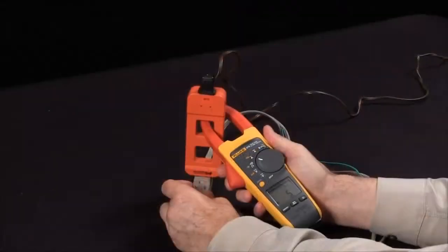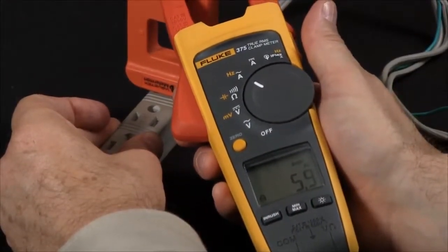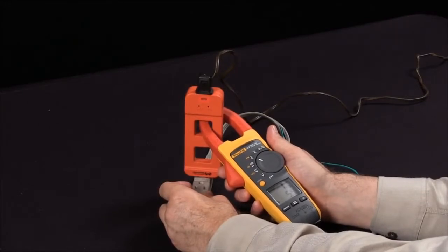I can go through my x10 winding, and there I'm reading just about 6 amps. So we're in good shape there. So this is how to properly measure a power cord and determine the current flow to any load attached to it.